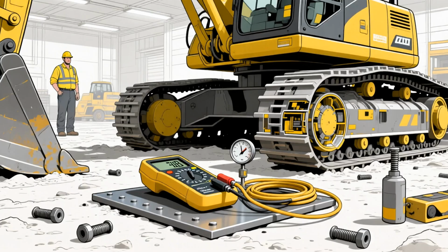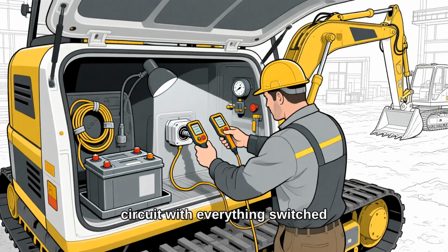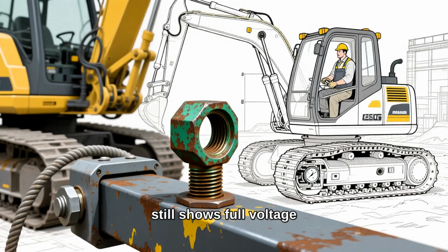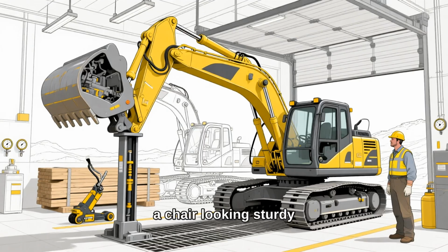Now, the meter. Most people use it wrong, and not with the wrong buttons, at the wrong moment. They probe a dead circuit with everything switched off, see battery voltage sitting there, and call the wire good. But a bad connection still shows full voltage when nothing's moving. It only fails when something asks for current. It's the difference between a chair looking sturdy and a chair actually holding you.